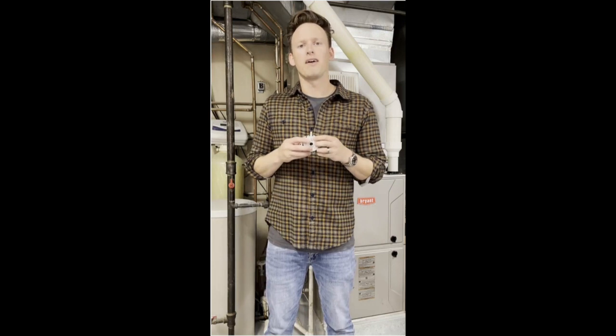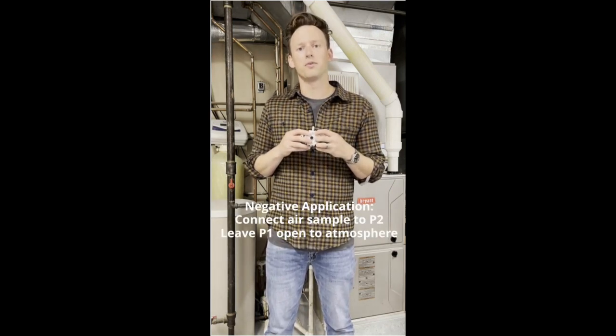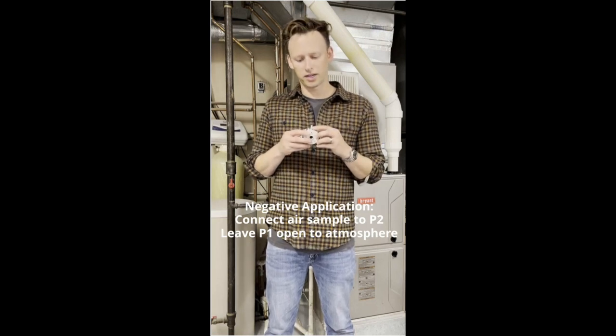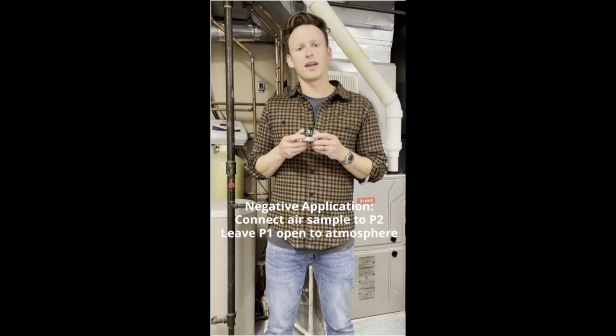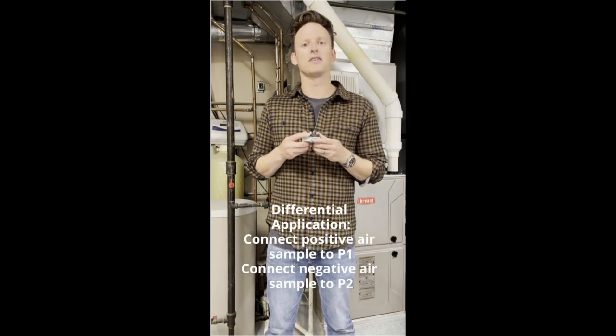If we have a negative application, we're going to connect our air sample to the negative P2 or gray air sample connection. And if we've got a differential application, we'll connect to both the positive and the negative.